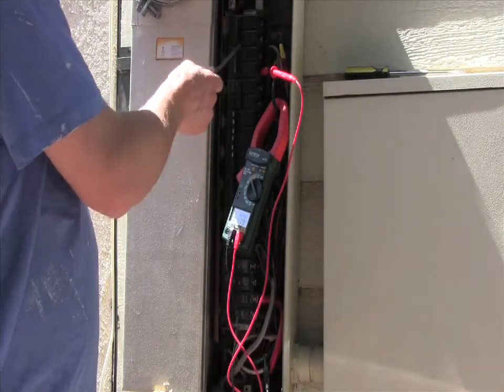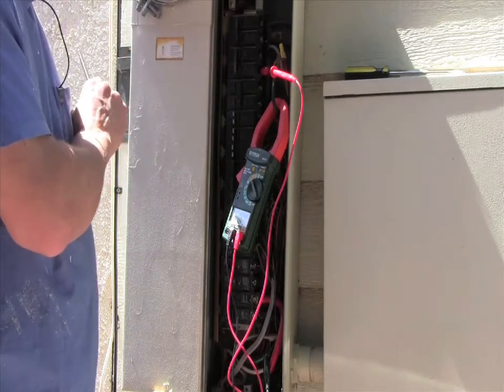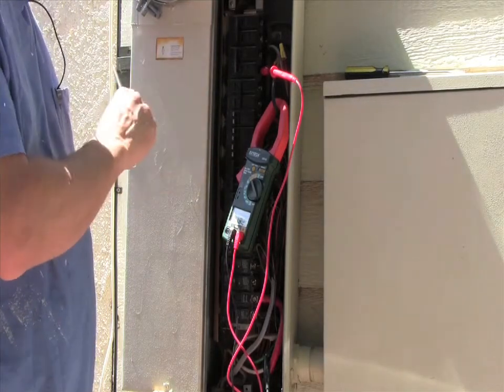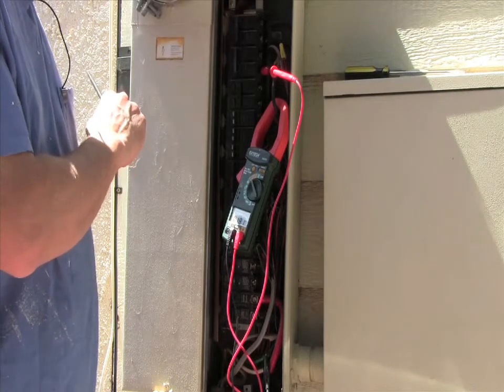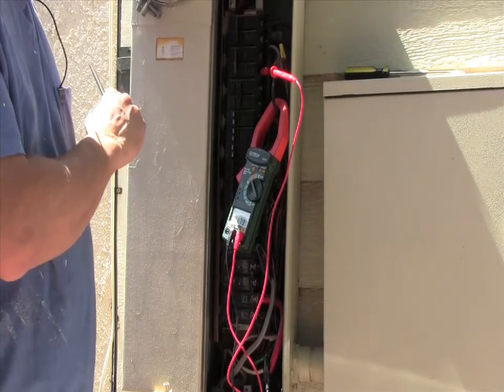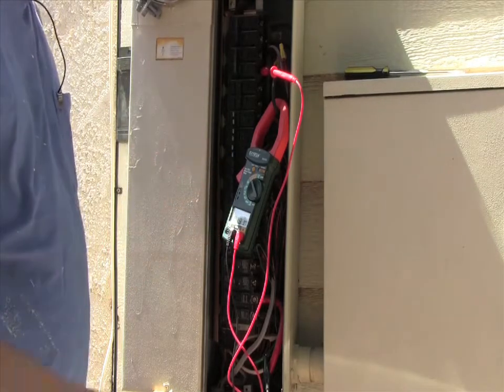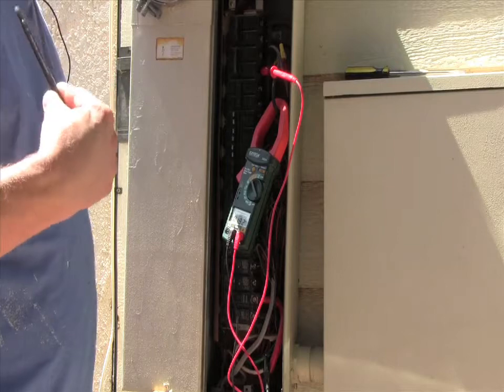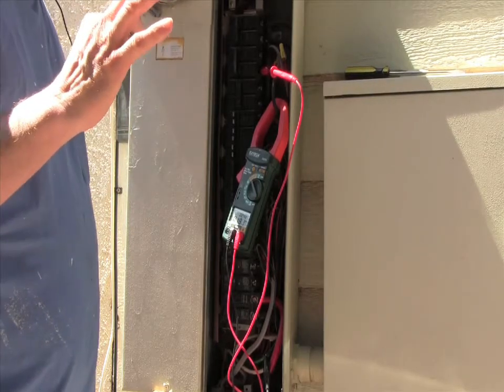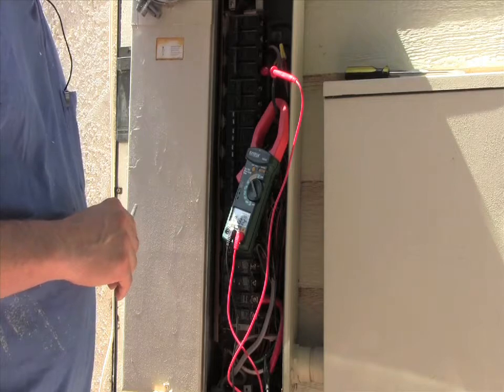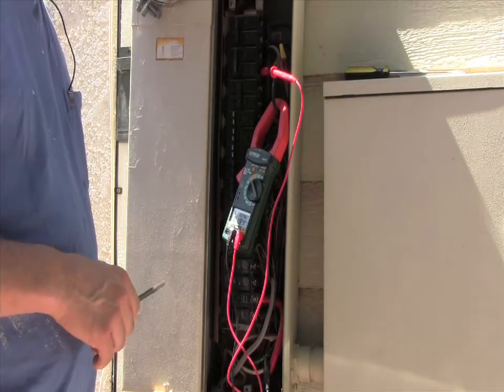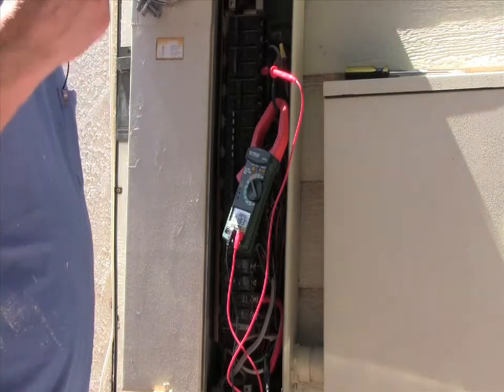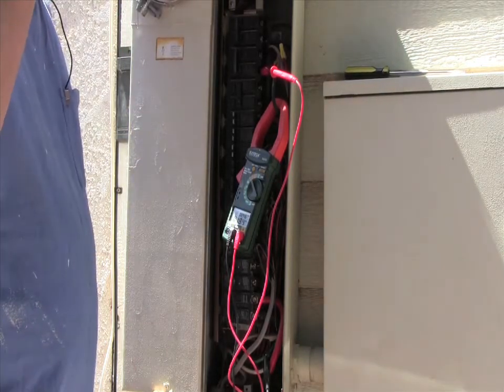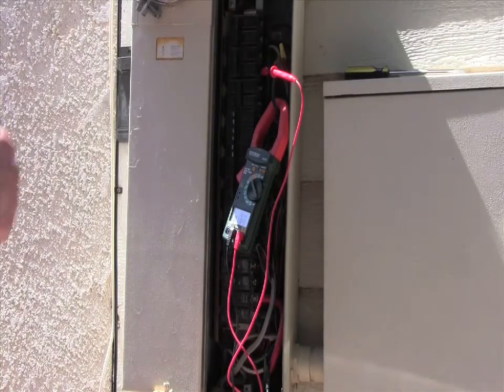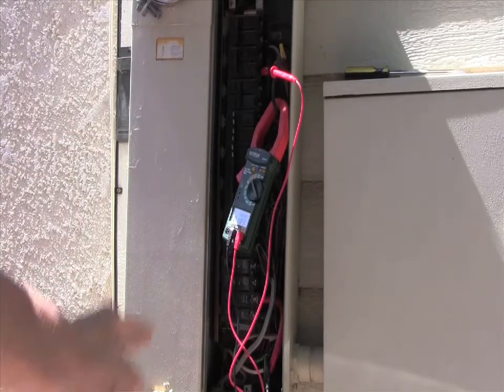When you shut the main power off, it may shut the power off to the thermostat, which is what happened to us. So I had to actually go back in the house, ask the customer to turn the air conditioner back on, or request to do it myself. Either way, if it doesn't come on in 5 minutes, some of the dual packs and some of the other systems have a 5-minute reset when the power's been turned off to the air conditioning units. So if you're on the roof and you throw the power back on, you'll hear it go click, you'll hear the condenser fan start blowing. Sometimes it can take 5 minutes for it to reset, for the cycle to complete the startup cycle.